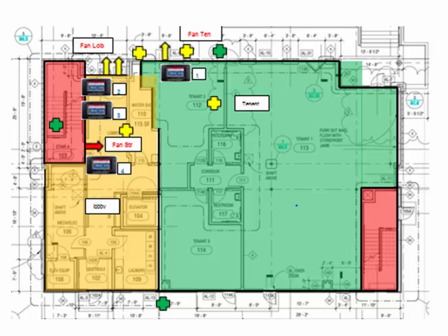To be consistent with our other testing, we did actually run a tube from our residential setup directly to outside. In this case, both north and south because it was a windy night. However, we could have actually run this blower door cruising at 0 pascal pressure with reference to the lobby, and then as the blower door setup in the lobby depressurizes that space to 50 pascals, the residential blower door would follow suit and ultimately get that residential section to 50 pascals as well.